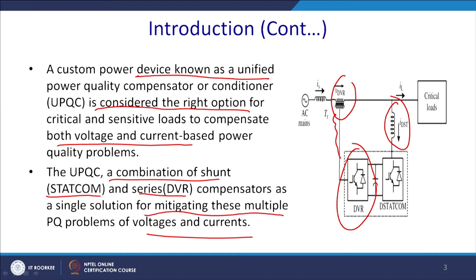Classification based on method of control, you may have reactive power injection, then we say that UPQC-Q. We may have UPQC-P, that is in-phase component, and UPQC-S, that is the apparent power based UPQC. In UPQC-Q, a DVR is used in series voltage injection in quadrature with the supply current with almost 0 active power injection. Then you say that it does not have any real power handling capability. Same way, if it is UPQC-P, the DVR is used in series injection in phase with supply current, it will inject only the active power.